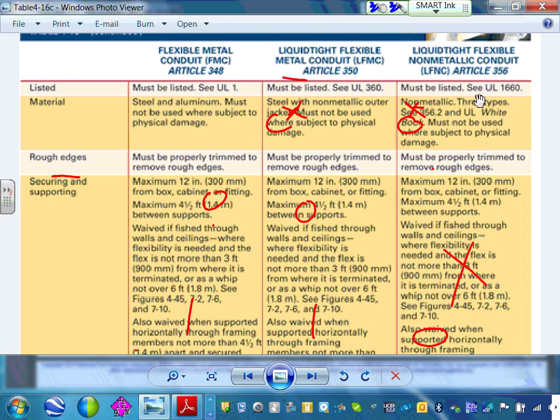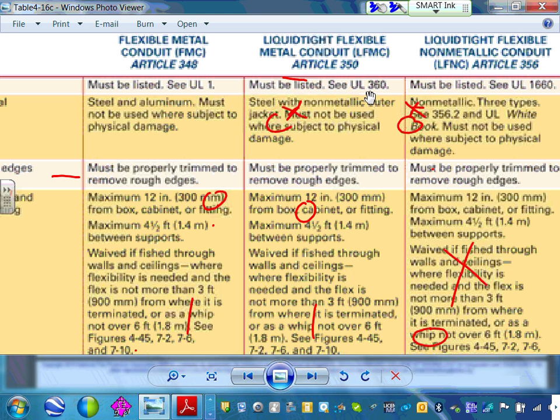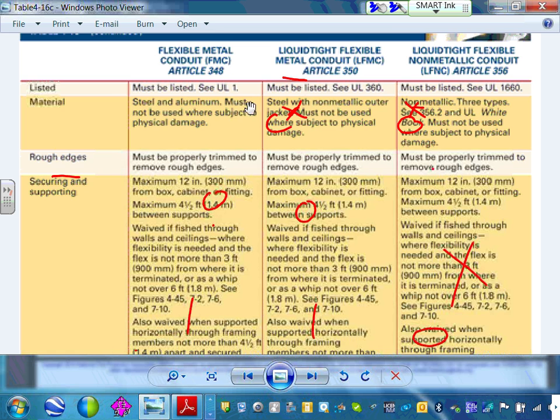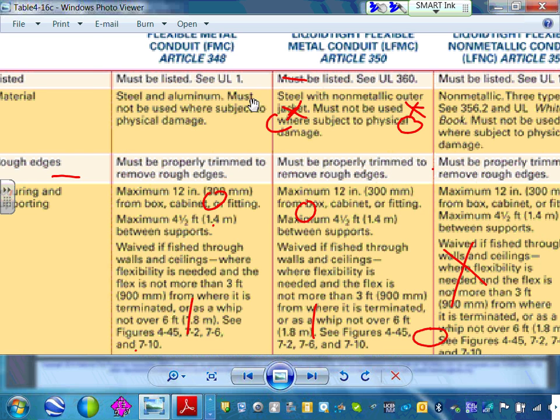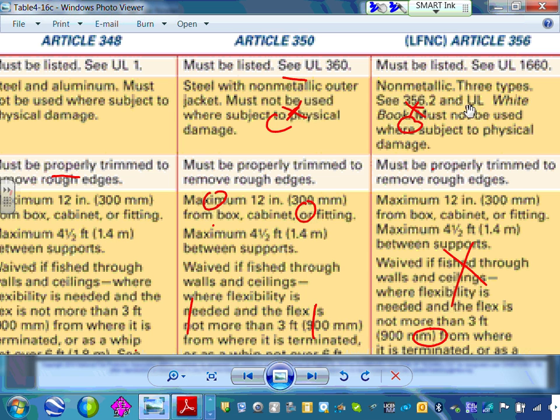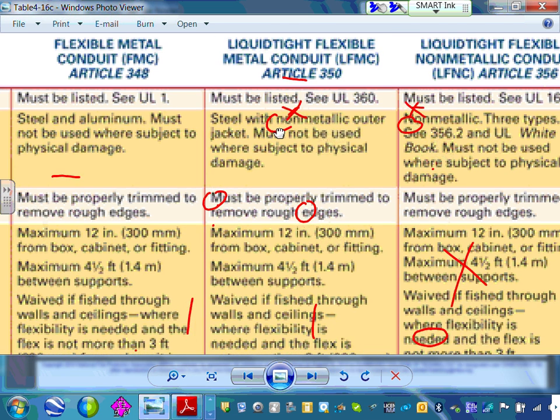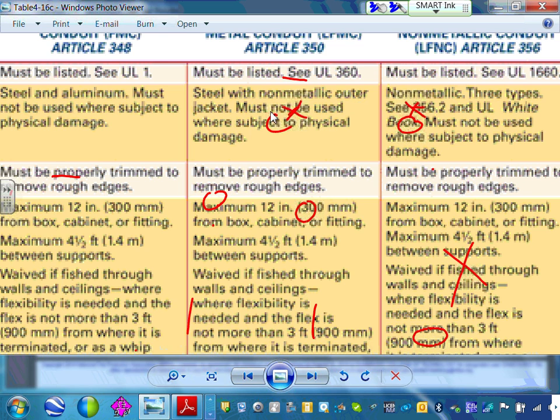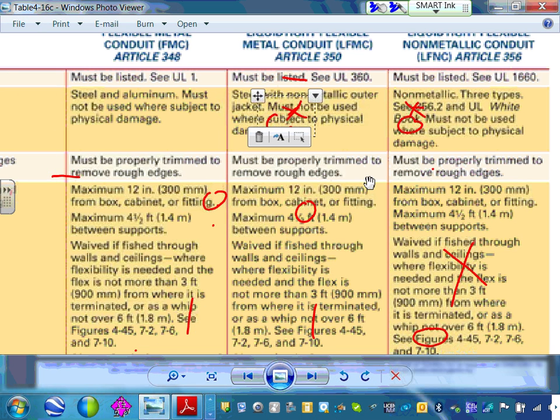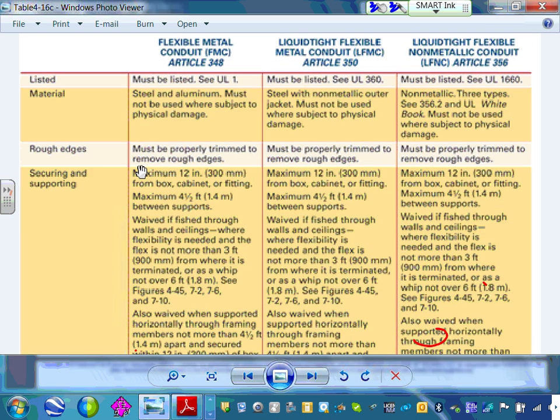Moving on. Should they all be listed? And what's the UL listing for them? UL 360 lists them. UL 1660, these are the listings for them. Material. You can have steel or aluminum for these. Obviously, the non-metallic is going to be non-metallic. This one is steel with non-metallic cover, the material that they make them from. So steel or aluminum for the flexible metallic conduit, steel with a non-metallic cover on it, and this is non-metallic material. Rough edges, do you have to smooth the rough edges? I hope so. Otherwise you're going to damage the insulation for all of them.